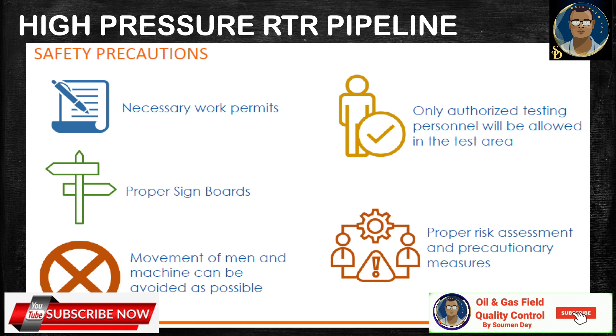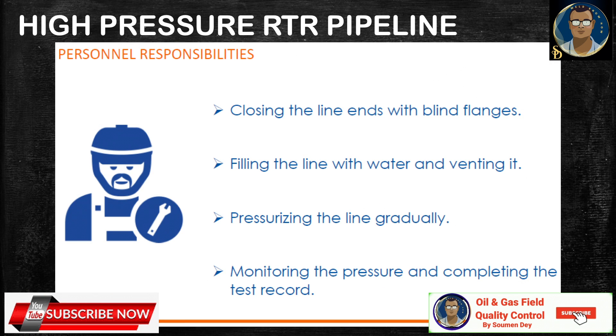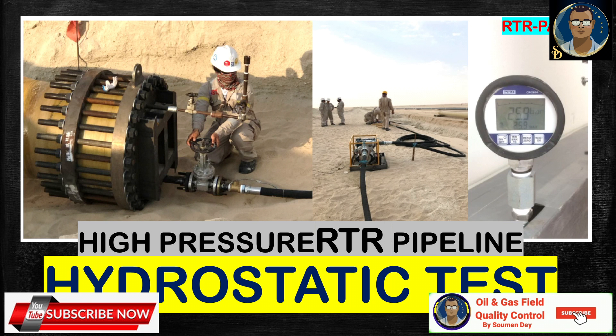Safety requirements include: obtaining the necessary work permit, posting proper signboards indicating 'Hydrotest in Progress', allowing only authorized testing personnel inside the test area, avoiding movement of machinery as much as possible, and conducting a proper risk assessment with precautionary measures. Job Safety Analysis (JSA) is one of the documents approved by all parties before any risk-related activities. Personal responsibilities include: closing line ends with blind flanges, filling the line with water and venting it, pressurizing the line gradually, and monitoring the pressure while completing the record.